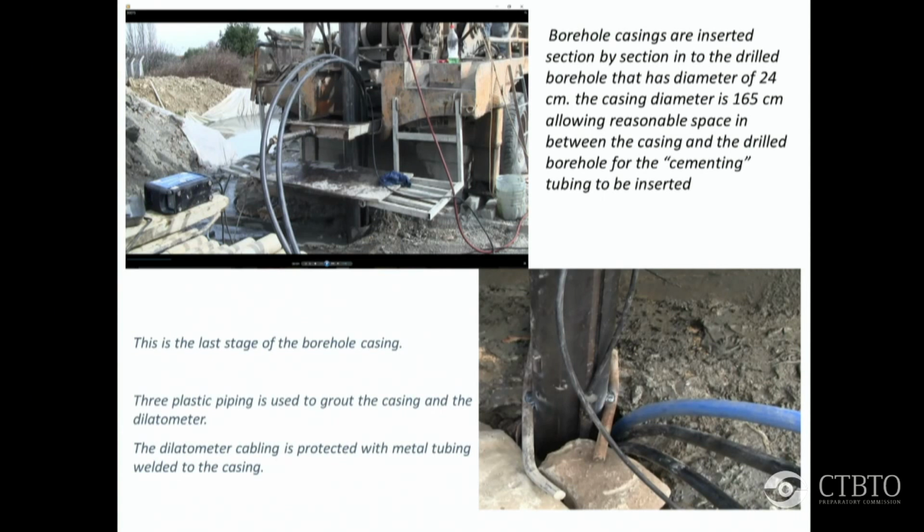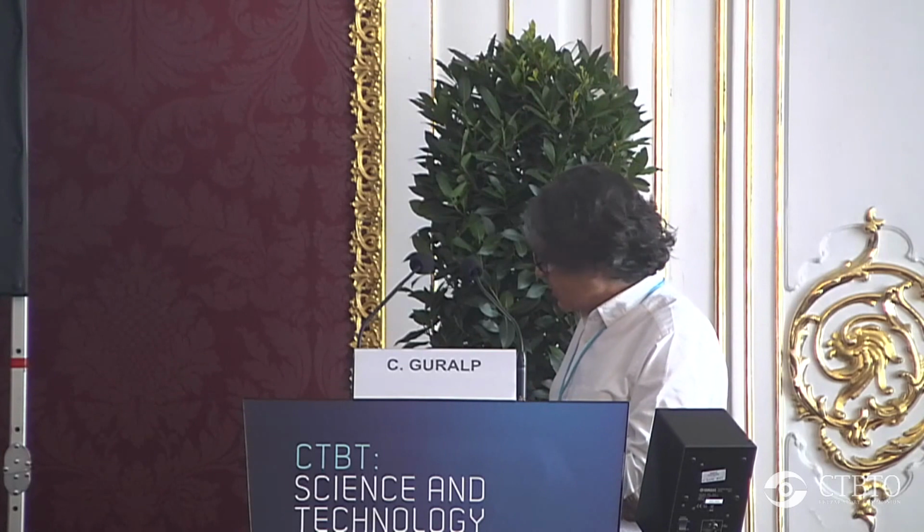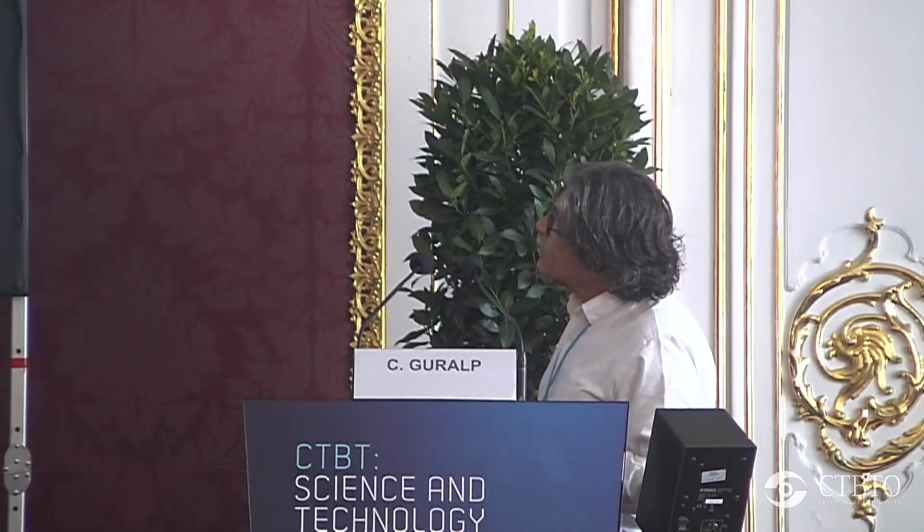Once the whole casing was inside the drilled borehole, the cement was injected from outside, and it came out at the top, all the way from bottom to top. And we think we really have cemented or grouted the instrument properly to our casing. And actually this shows, especially when you look at the high-frequency performance of the instrument.